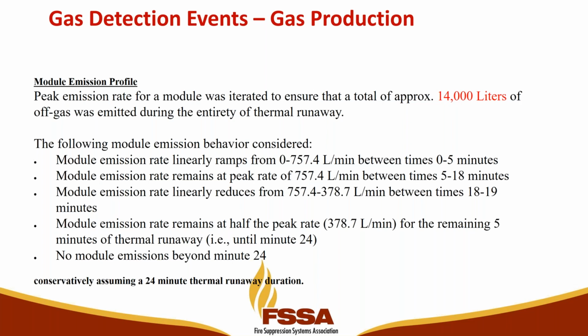So that 14,000 liters broke down into emission rates over time, because this is somewhat of a bell curve. As one fails, it propagates to the next, and to the next, and then the first one starts tapering off while the others enter the range of providing gases. Overall, we had a bell curve of emission rates for a rack over about 24 minutes.